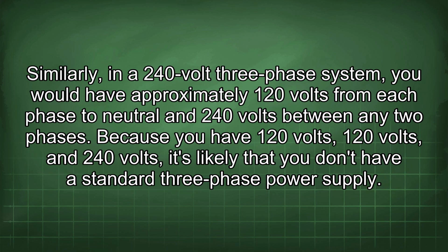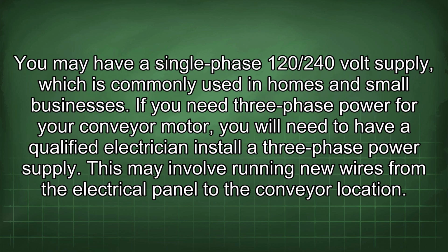Similarly, in a 240-volt three-phase system, you would have approximately 120 volts from each phase to neutral and 240 volts between any two phases. Because you have 120 volts, 120 volts, and 240 volts, it's likely that you don't have a standard three-phase power supply. You may have a single-phase 120/240 volt supply, which is commonly used in homes and small businesses.